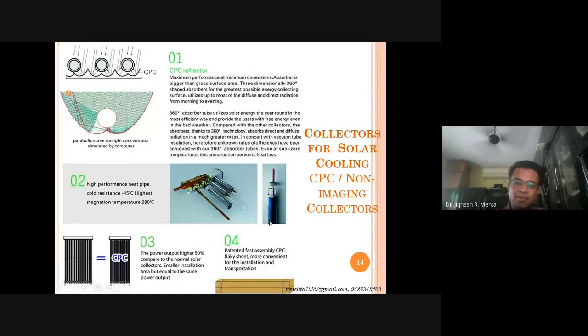As you can see, you probably know about the evacuated tube, the double glass tube. There are two concentric tubes in this, and the outer surface of the inner tube is acting as an absorber, and the heat is conducted through the inner tube to this fin, and this fin provides it to the evaporator section of the heat pipe, and then it finally goes into this condenser portion, and it indirectly transfers the heat to the water flowing in the manifold. So this is one scheme that may be used for industrial process heating, the evacuated tube collector with heat pipe, and in this case even the CPC reflectors have been put.